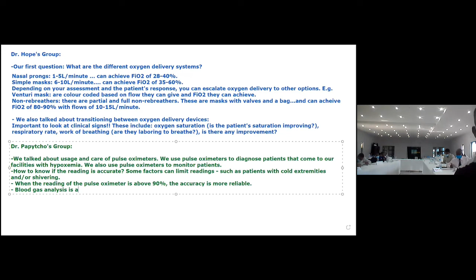So if you want to compare the saturation on the pulse oximeter and then you draw blood from the arterial line of the patient to do a blood gas analysis, it will give you a reading which is close to the actual reading on the pulse oximeter. The range of difference there is very minimal, less than 2%. And then it's higher when it's below 90% of saturation.